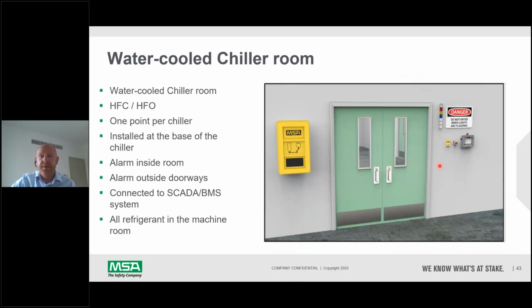So at the doorway, we have the alarm system. We have a siren. We have different light warnings for the level of the leak. And then we have a display here as well, which the operator can see, showing the gas levels at different locations in the room. Then we also have a self-contained breathing apparatus here.